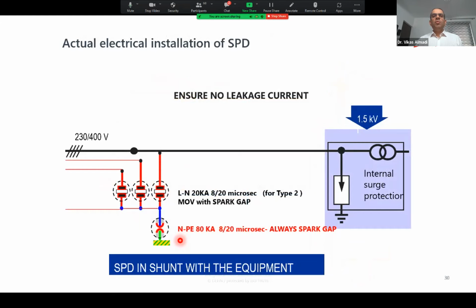Now for type 2 SPDs, we have to talk about the 8/20 microsecond surge and total current. Let us say if we are using the SPD for 20 kiloampere, same rule, multiply by 4, you have to use the neutral to earth SPD as 80 kiloampere. But if you are using 40 kiloampere as the neutral to earth SPD, then this is divided by 4. 10 kiloampere is sufficient, because these two ratings should match. Otherwise, there is no point giving one of higher rating and another of lower rating. This is a multiple of 4 because of the wiring, not because of any other mathematics. Simple, 1:4.